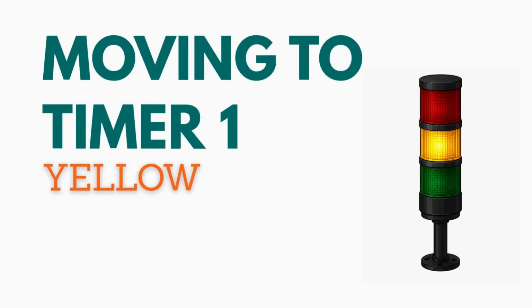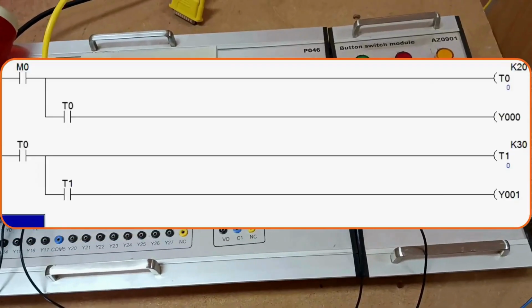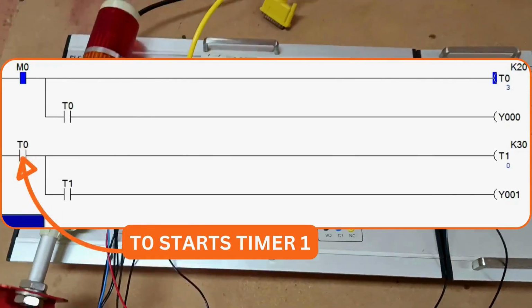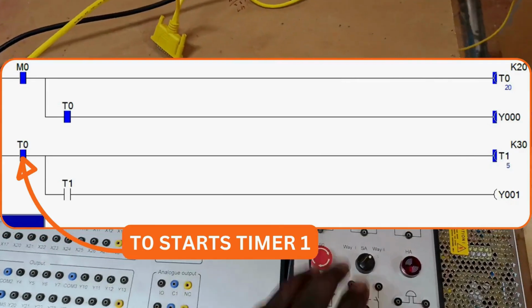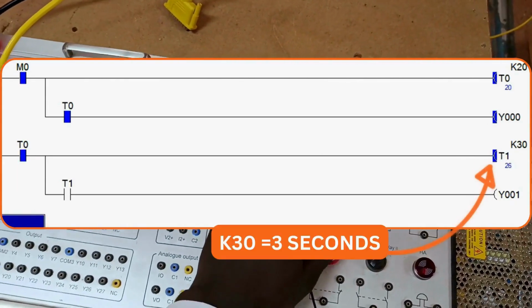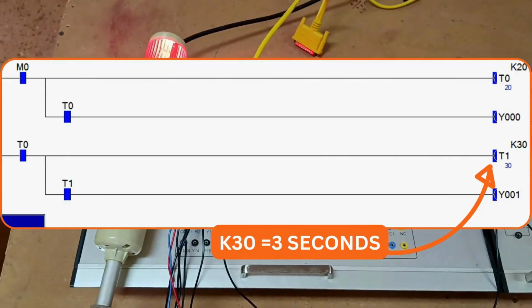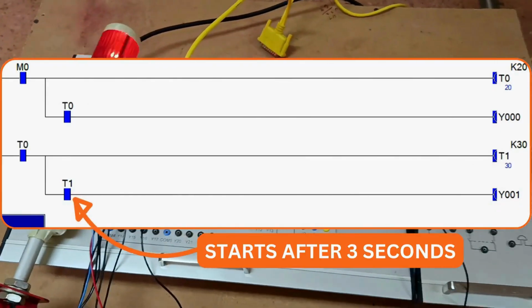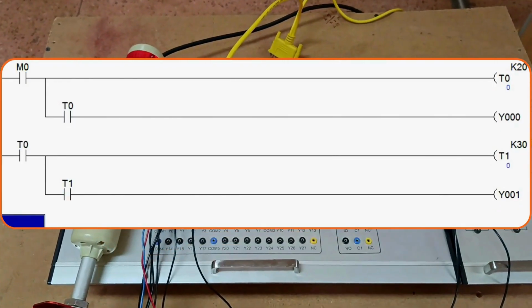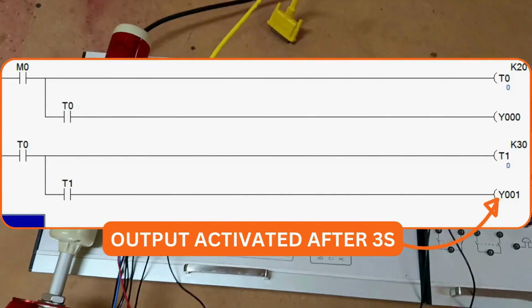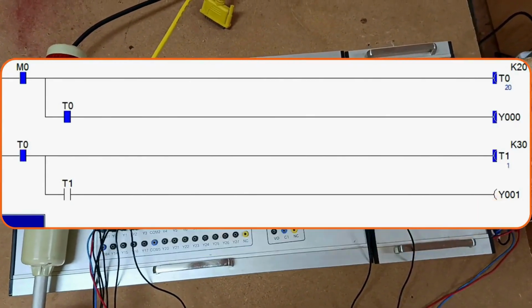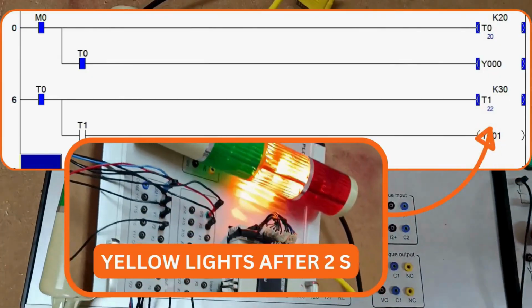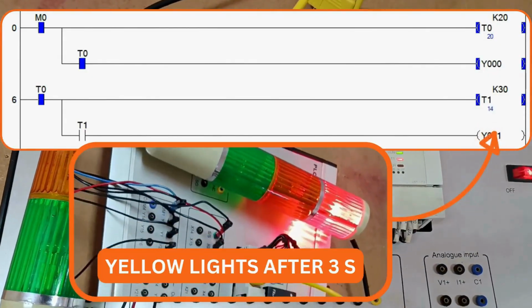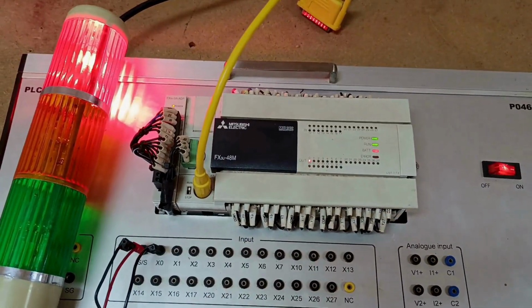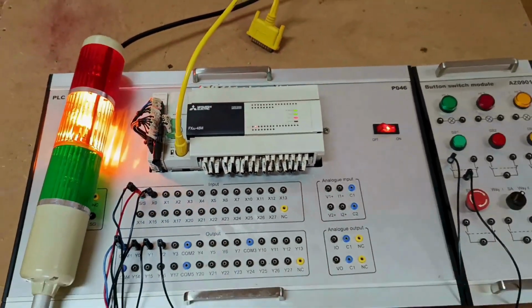Now let's move on to the second stage. Instead of allowing T1 to start independently, we connect it to the completion of T0. So T0 becomes the condition that enables T1. T1 uses K30, which is 3 seconds in this example. Its normally open contact is used for the yellow output Y1. This is what gives us a true sequence. The second stage cannot begin until the first stage reaches its required condition.